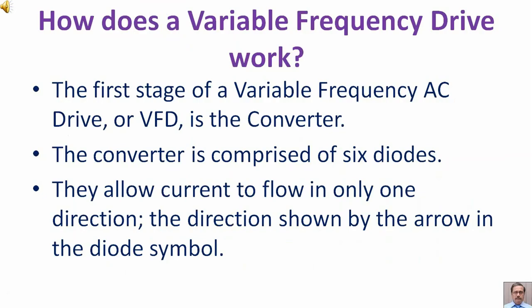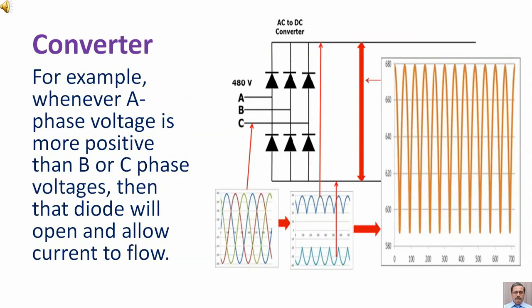How does a variable frequency drive work? The first stage of a variable frequency AC drive or VFD is the converter. The converter is comprised of six diodes. They allow current to flow in only one direction, the direction shown by the arrow in the diode symbol. For example, whenever A phase voltage is more positive than B or C phase voltages, then that diode will open and allow current to flow.